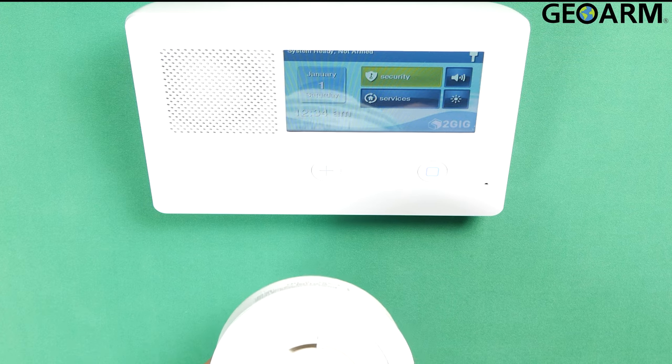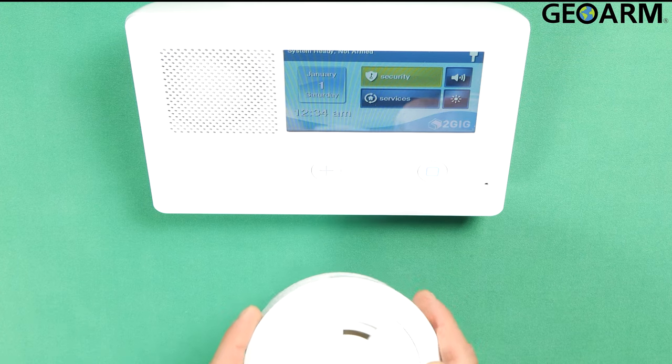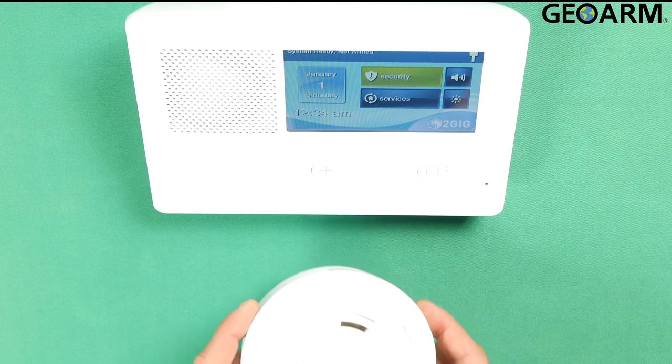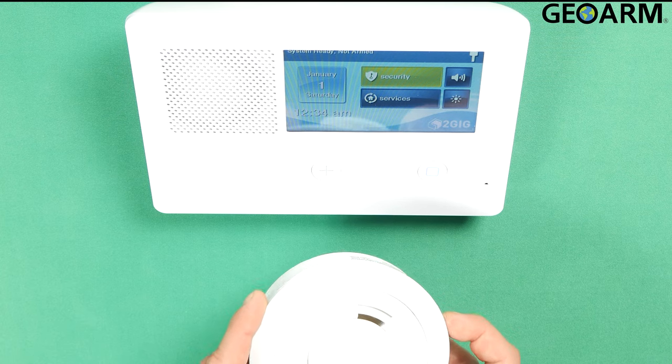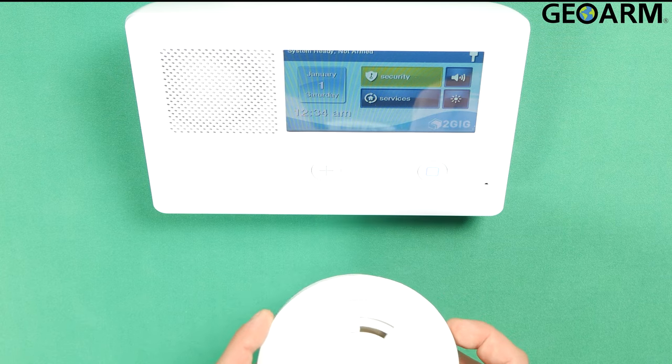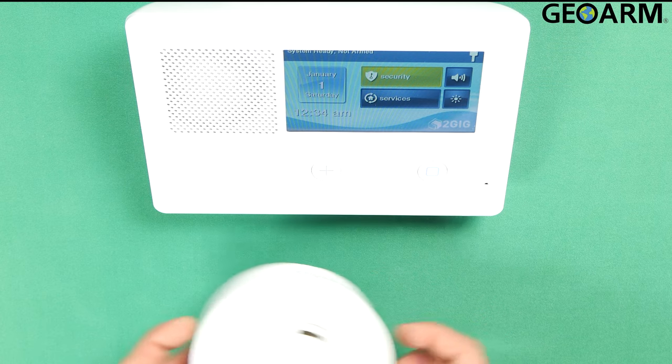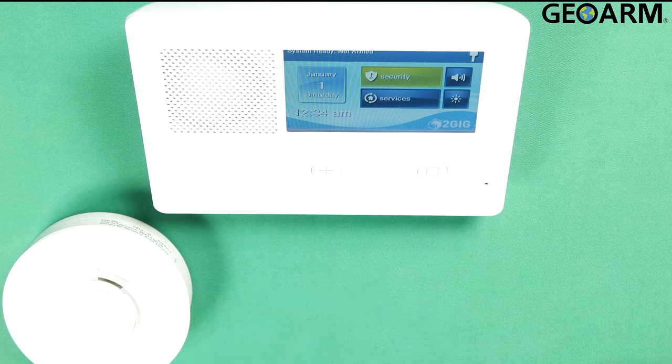Now the first thing you want to take into account is this is an E-Series device. The equipment code will start with the number 2. In this case it is 2058 for the equipment code and the loop number will be loop 1 for the smoke detector. So we'll go ahead and we'll start getting this thing learned in.